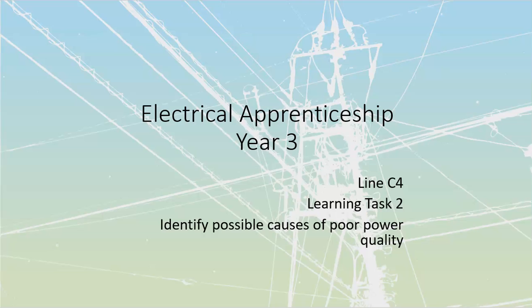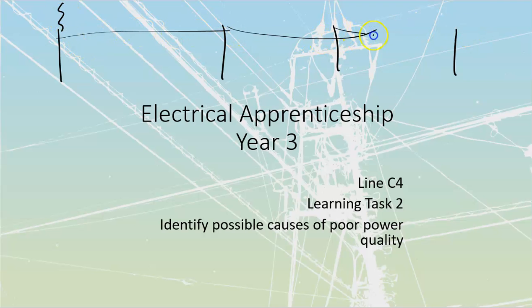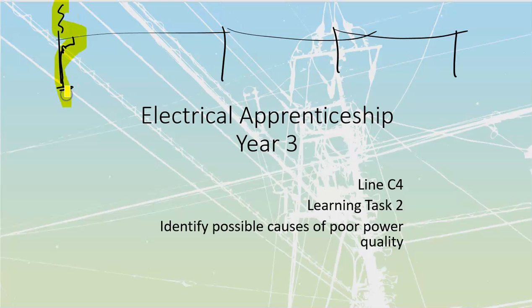These surge arresters can deal with a lightning strike a couple of poles away, minimum. If lightning strikes over here, with lines running pole to pole, I'll probably be fine further along, but closer in, even with a surge arrestor diverting it to ground, there's still enough coupling and other issues present on the line that I'll still feel it. As I get further from the strike, it attenuates.